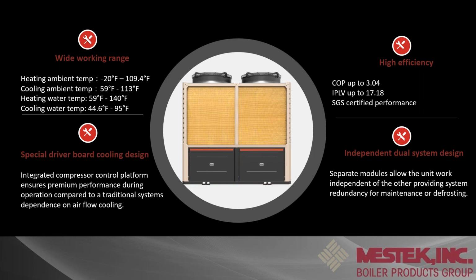On this product, as you can see, there are 2 fans. It appears like it's 2 coils and then 2 boxes. They're separate modules. So let's say you had one compressor fail, the other one would still operate. So there is built-in redundancy on this product. And now that I'm talking about the compressors, there are 2 15-horse compressors on this product, independent refrigeration circuits.